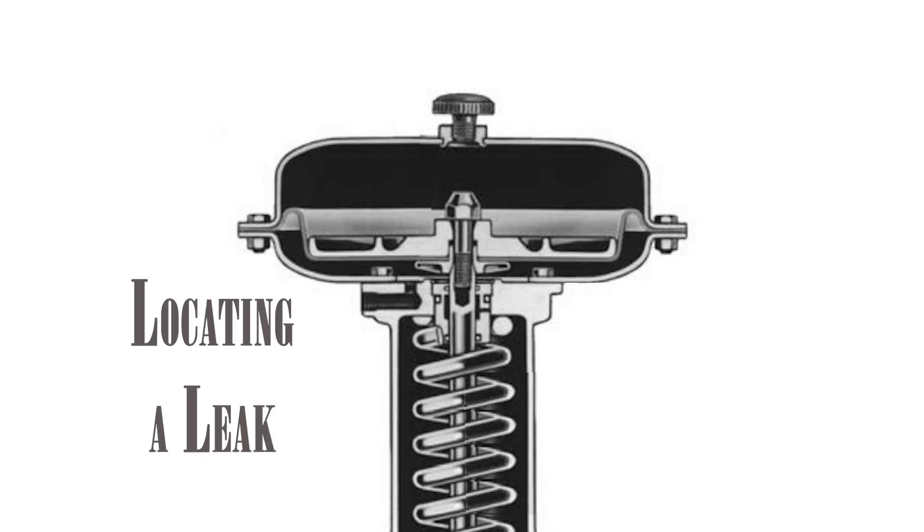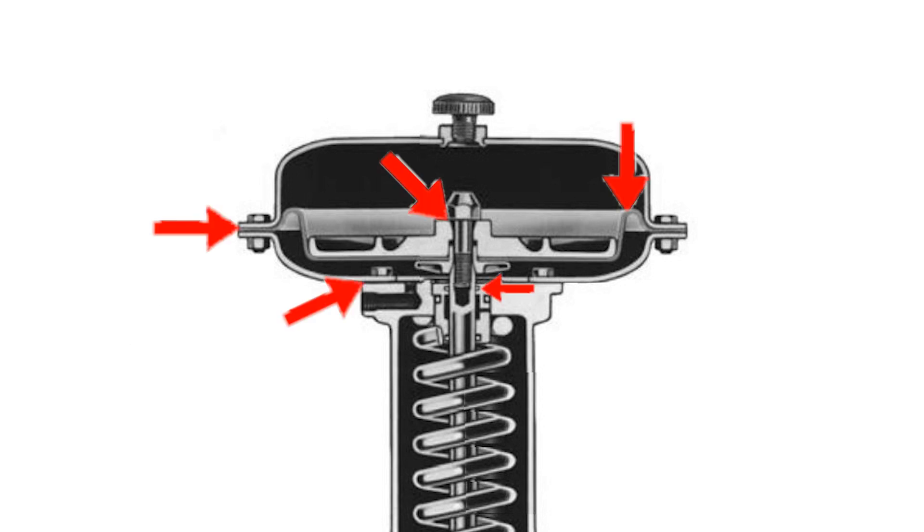There are numerous potential leak points on a Fisher rising stem actuator. The molded diaphragm is sandwiched between the upper and lower case of the actuator.